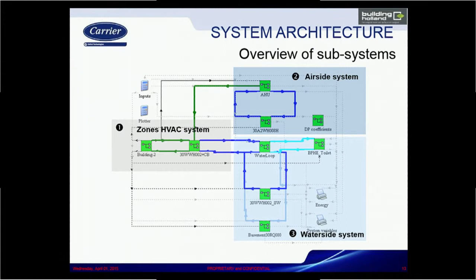So here, the system proposed was still based upon a traditional chilled beam approach, but modified. What we wanted to do considerably differently is have a variable air volume approach on the ventilation air. In order to do that, and in order to reduce energy, we wanted to eliminate the traditional use of variable dampers to adjust the air volume based on occupancy. By doing this, we estimated we could save about 30% of the fan energy that's normally lost at those dampers, and in the process reduce the energy needed by the air handling unit in distributing the ventilation air. So we were looking for a smart ventilation module. Optimize the ventilation, manage it based on occupancy with CO2, and also optimize the free cooling possibilities, deliver more air than necessary when outdoor conditions permitted it.